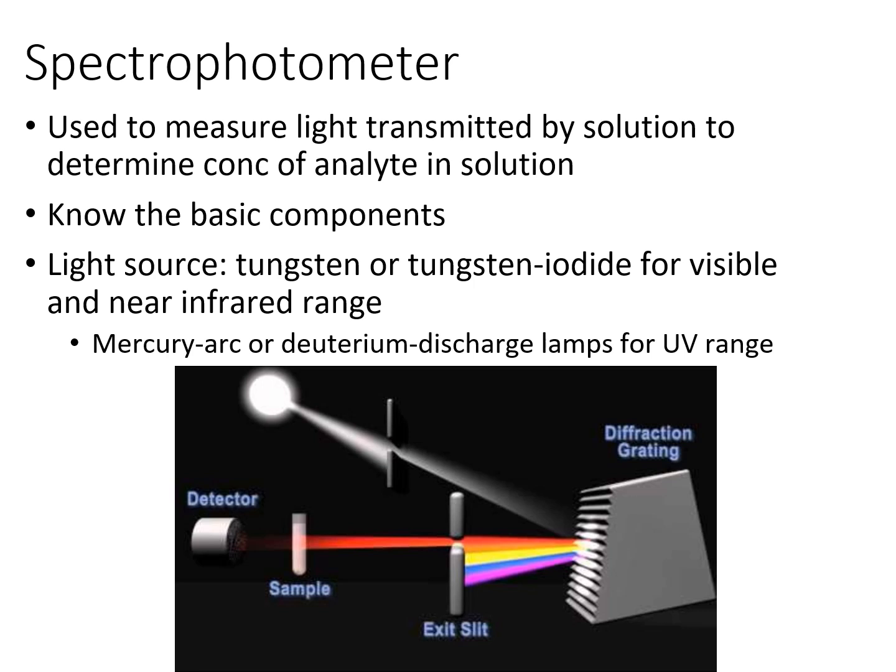So how this works: light is emitted and passed through the monochromator to isolate one wavelength. This light passes through the sample solution in a cuvette. Some light is absorbed by the analyte, and the remainder is transmitted. The detector measures light intensity and sends data to the readout. And then the absorbance is calculated and used to determine the concentration by either the Beer's law equation or that calibration curve.